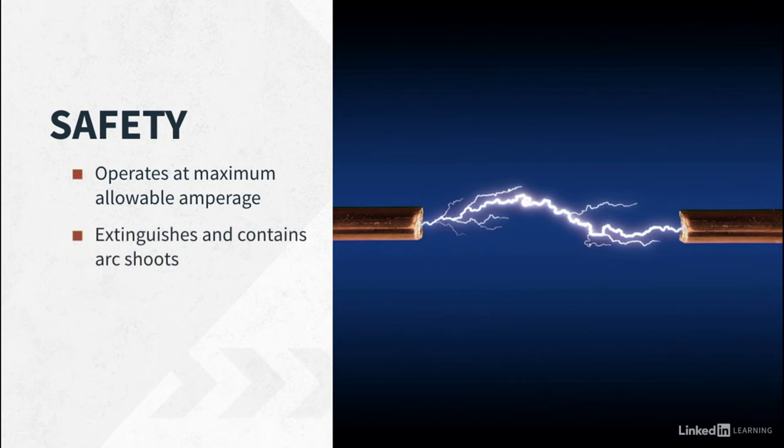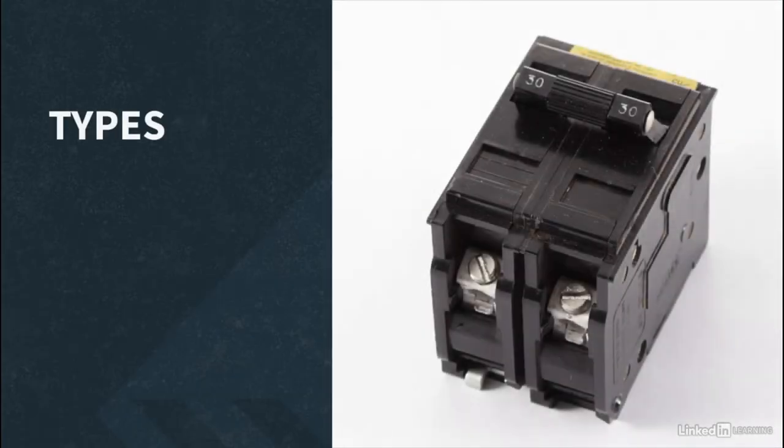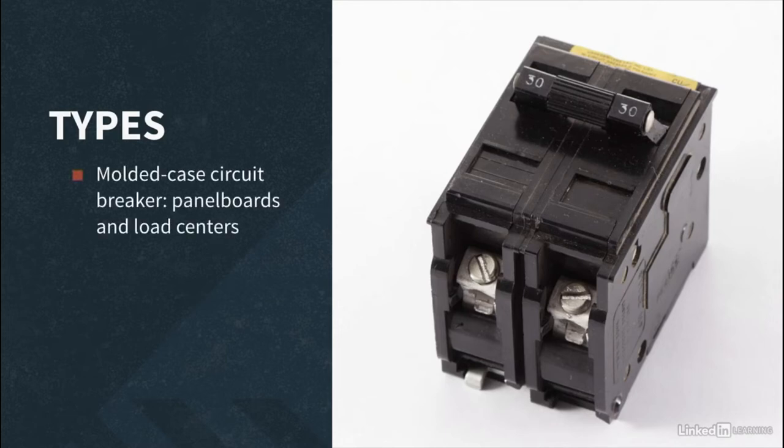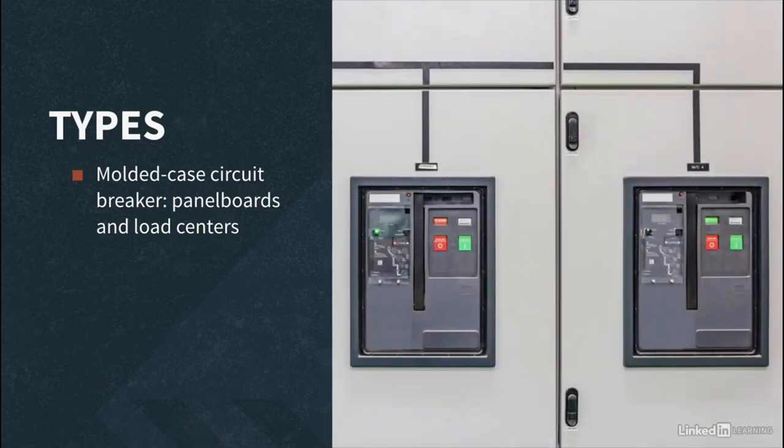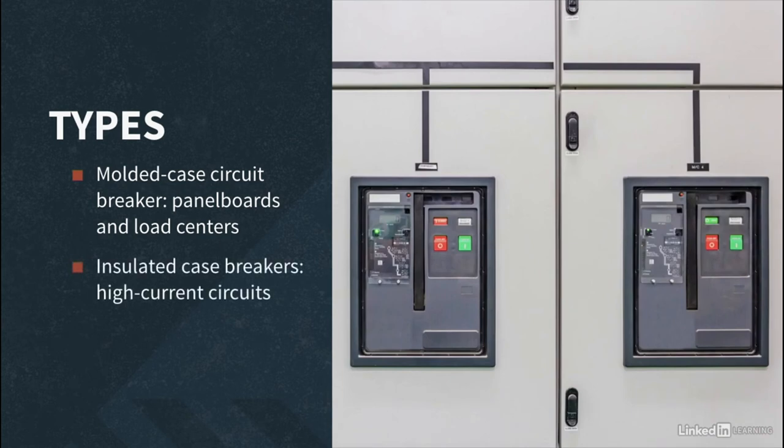Arc chute. Sometimes circuit breakers have a method to extinguish or contain an electrical arc. This is known as an arc chute. There are a few types of circuit breakers that you will see used in electrical distribution. The two main types are smaller molded case circuit breakers, like this one, used in panelboards and load centers, and larger power circuit breakers, also known as insulated case breakers. These are used on large circuits and equipment that use high current.